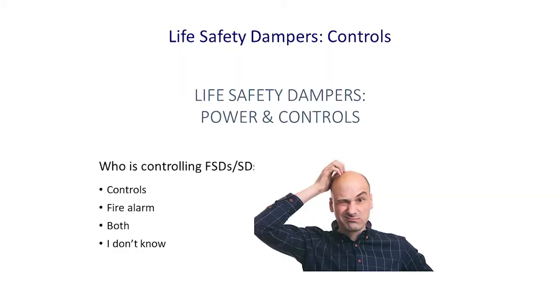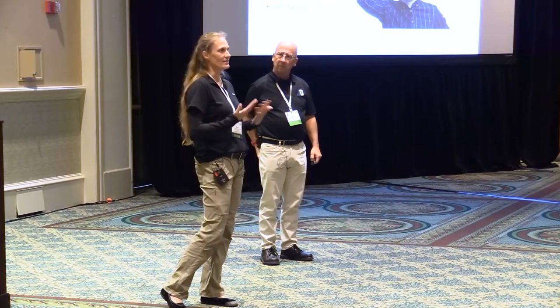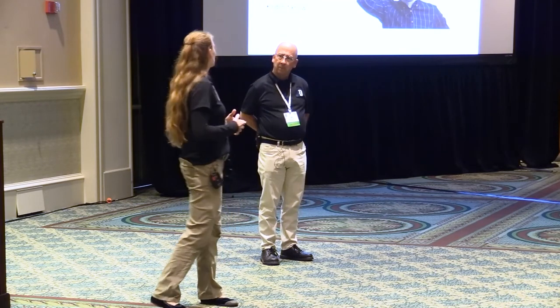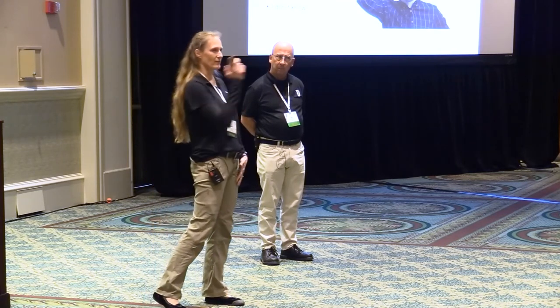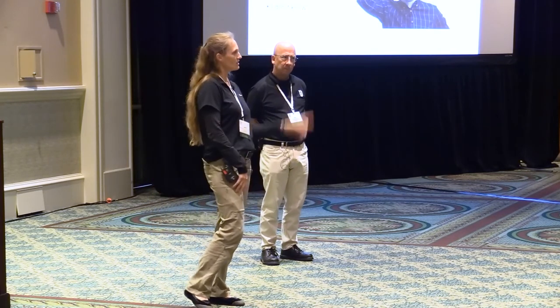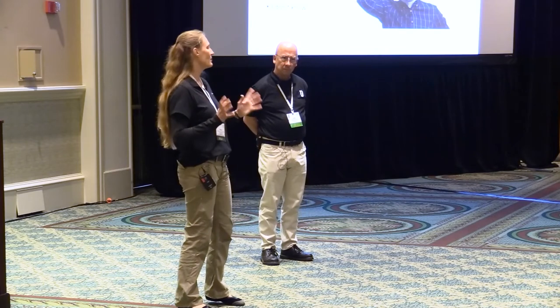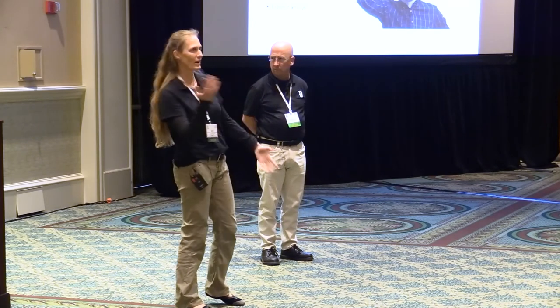So life safety dampers, who controls them? We now talk about this at our kickoff meeting, or in this controls page turn, or whatever's earlier, or even a design review, ideally a design review if that's earlier yet. But so often at the end of projects, controls is saying fire alarm's controlling those, and fire alarm says controls is controlling those, and then it's a big, big deal at the end because wires aren't pulled.